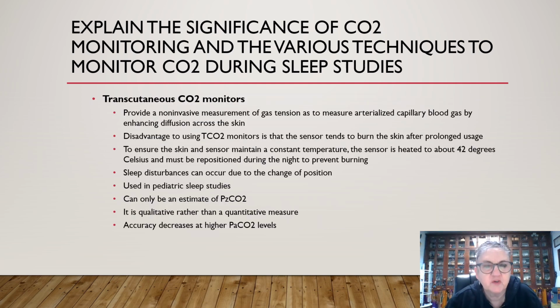Another form of measuring CO2 is with the transcutaneous CO2 monitor. It provides a non-invasive measurement of gas tension, to measure arterialized capillary blood gas by enhancing diffusion across the skin. There's a disadvantage to using the TCO2 monitors: the sensor tends to burn the skin after prolonged usage.